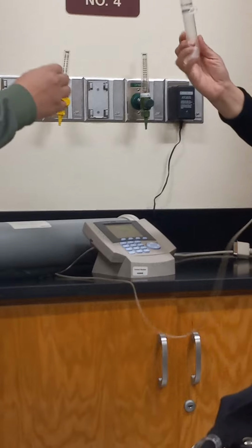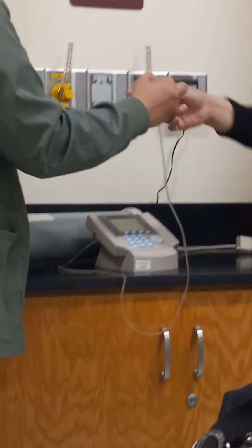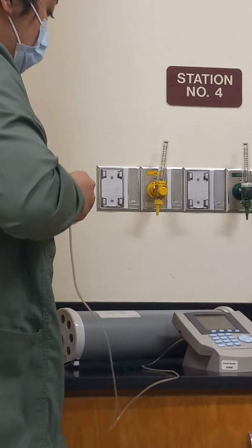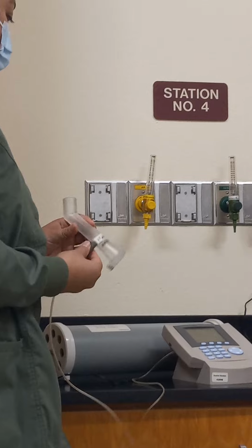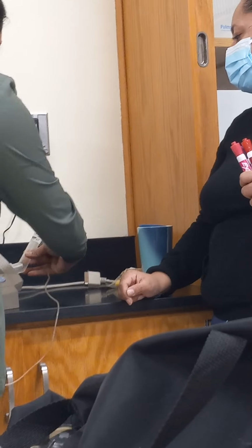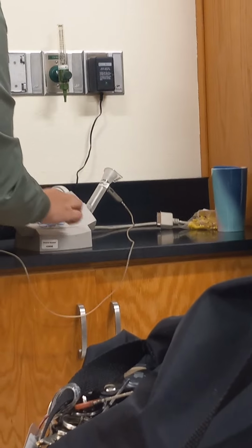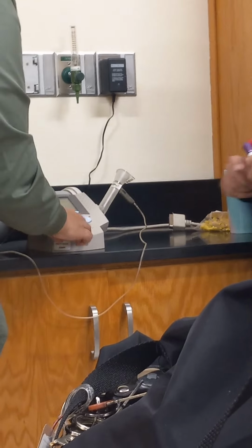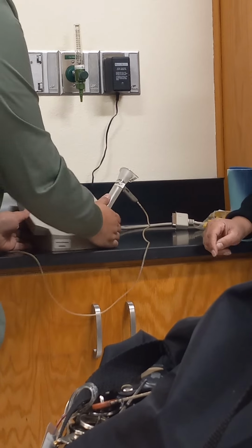Here's my flow sensor, which would be my mouthpiece. Attach this to your flow sensor. The mouthpiece is going to be like our patient, and she's going to attach it to my syringe over here. Go ahead and do number 5, cal check. It's not touch screen, and you have to put the number of the flow sensor, so just put your number.